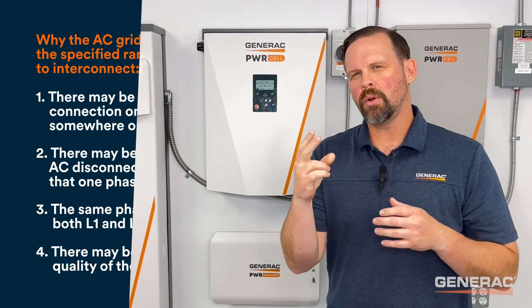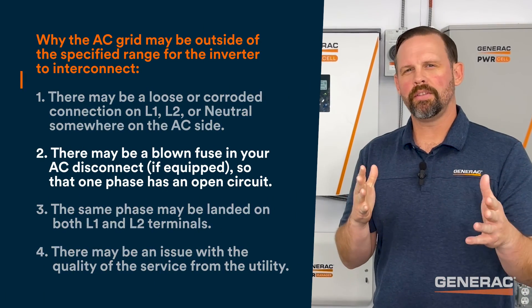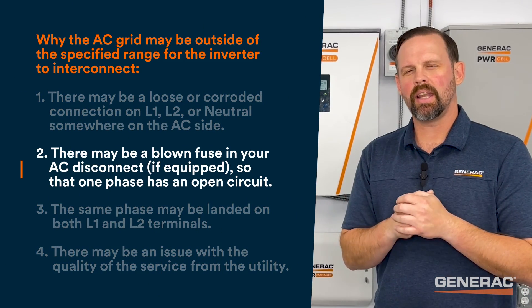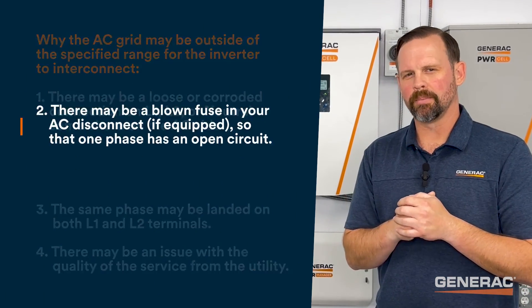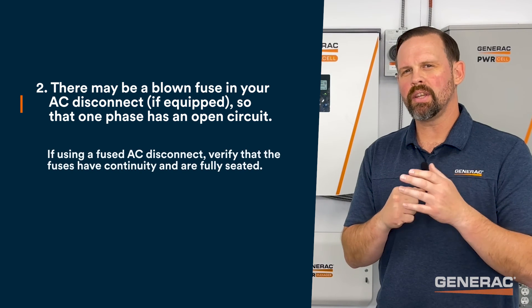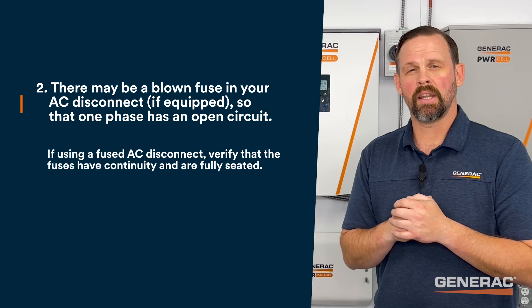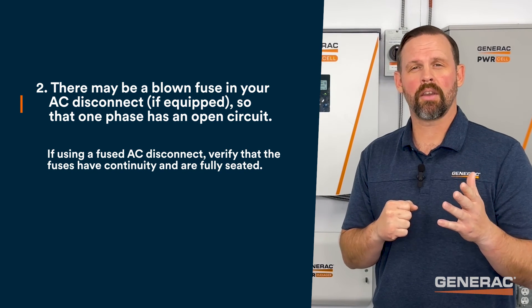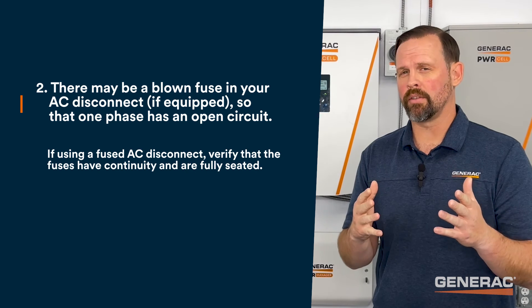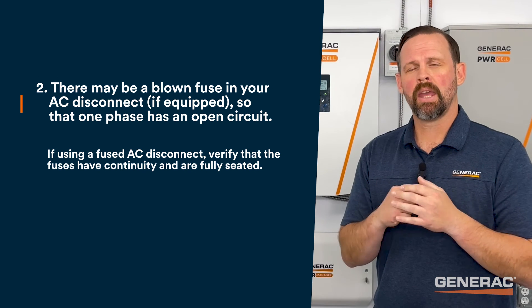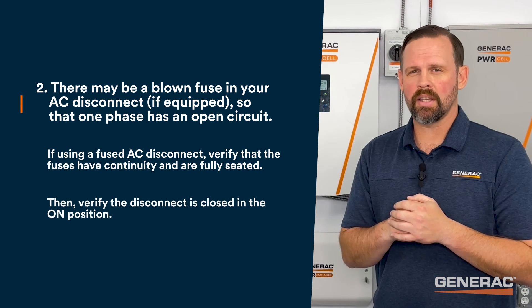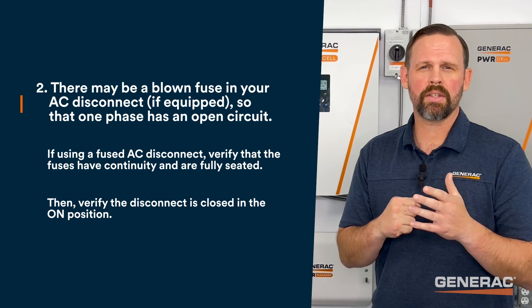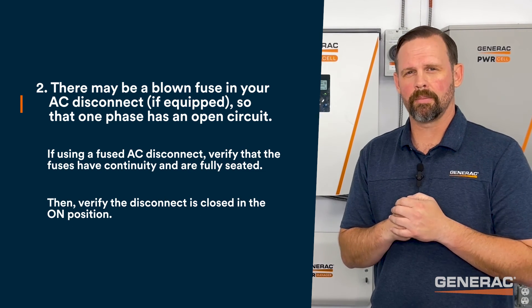Reason number two has to do with your fused AC disconnect if equipped. If you're using a fused AC disconnect on the inverter circuit for interconnection, ensure the fuses have continuity and are fully seated. Then ensure the disconnect is closed in the on position.